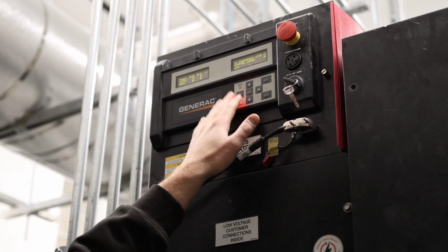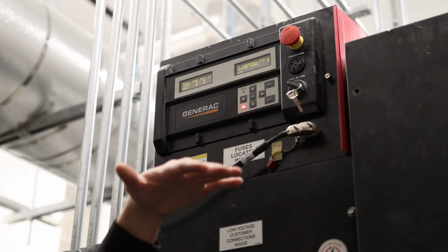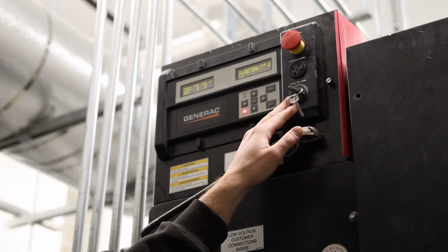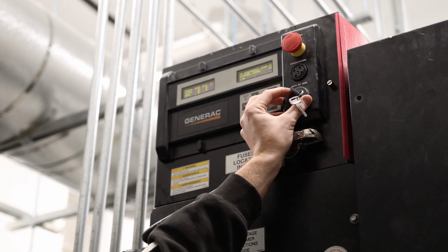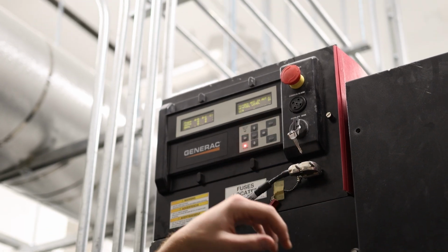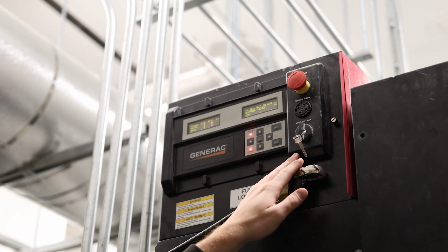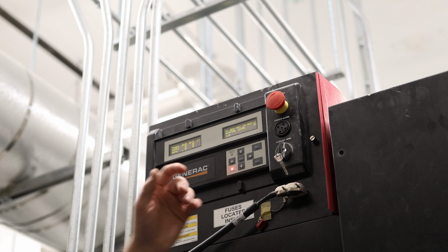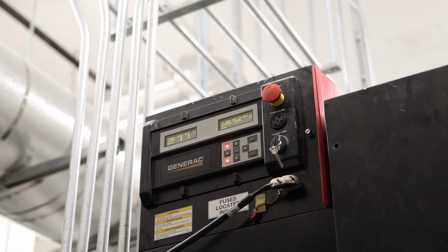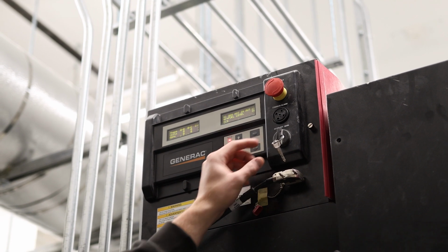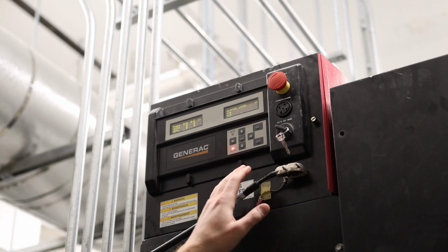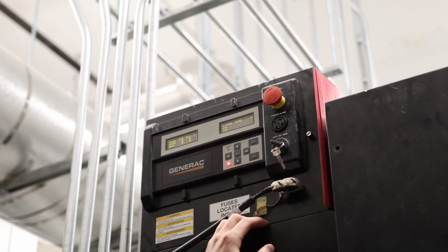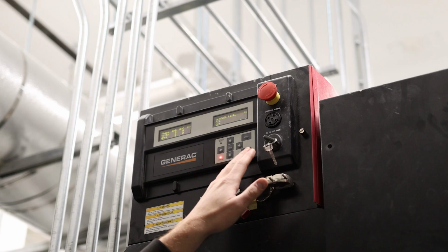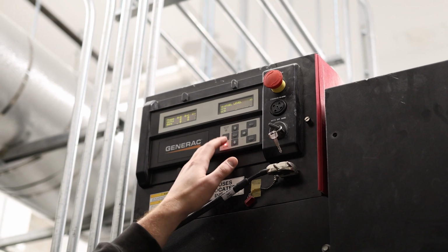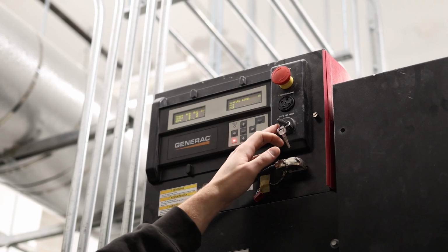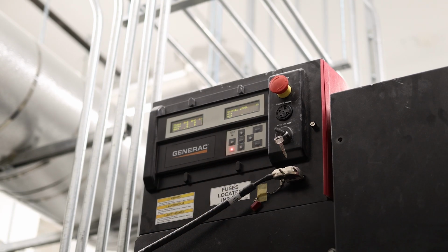To reset a shutdown alarm, so an alarm that would stop the unit's operation, the key switch needs to be turned to the off position, into the middle, and then it can be acknowledged. Whenever the key switch is in the off position, it will also throw an alarm, letting you know that the generator is not ready to run, essentially. Once the key goes back to automatic, that non-auto alarm will clear. So you get an alarm, come out to the unit, see what the alarm is, try to reset it, flip your key to off, hit enter, try a restart.